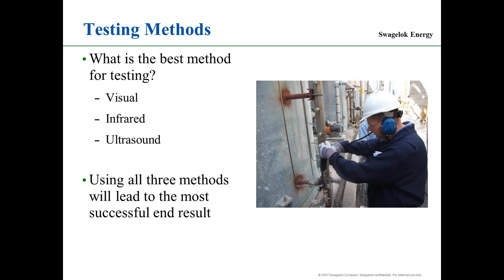I walk in plants all the time and say, that steam trap is bad. And so how do you know that steam trap is bad? It's upside down, okay? Visual. So you really want to use all three methods.